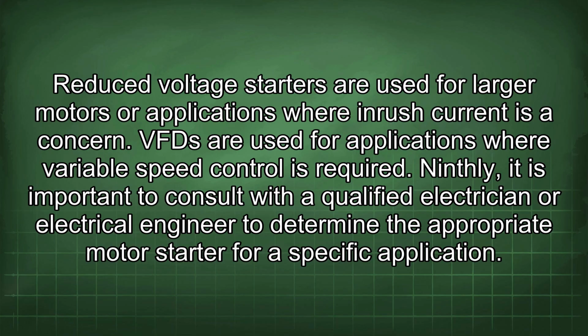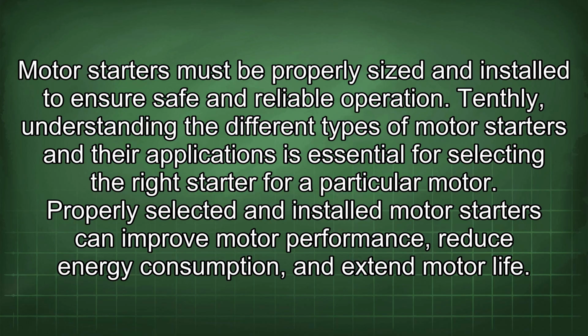Reduced voltage starters are used for larger motors or applications where inrush current is a concern. VFD are used for applications where variable speed control is required. Ninthly, it is important to consult with a qualified electrician or electrical engineer to determine the appropriate motor starter for a specific application. Motor starters must be properly sized and installed to ensure safe and reliable operation.